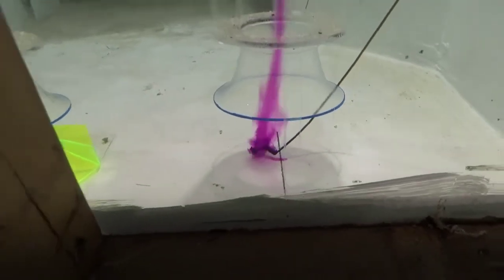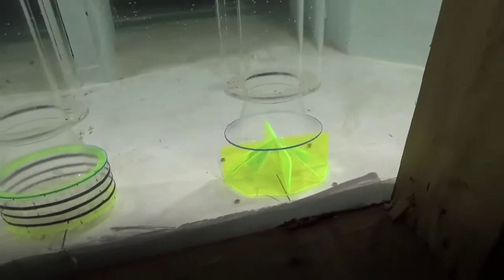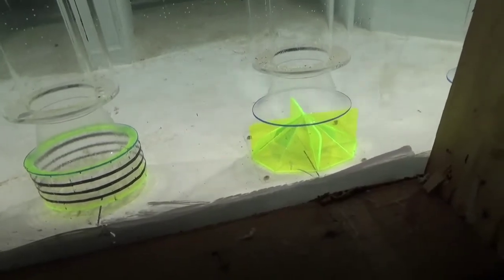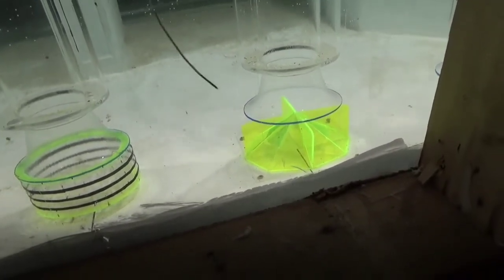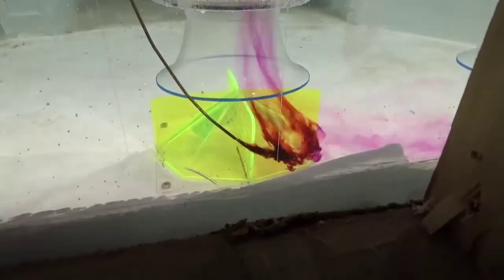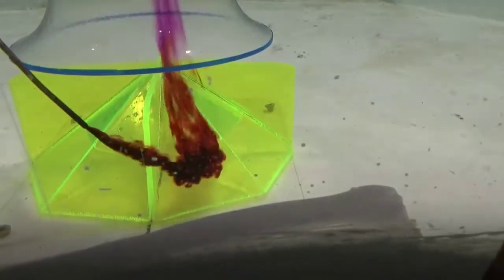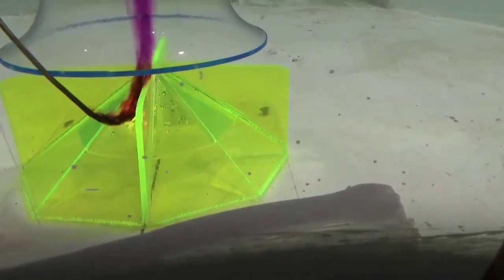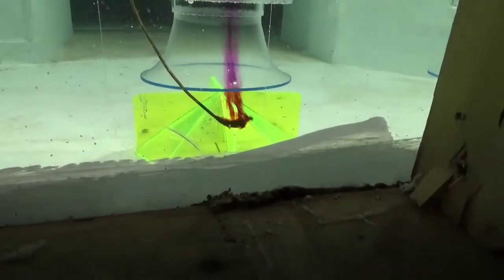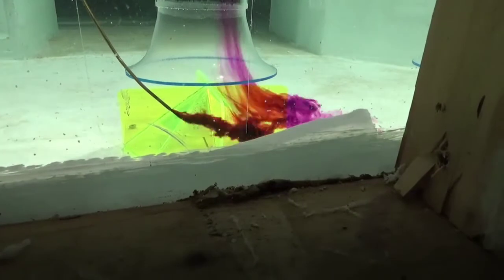Strong floor vortex. Let's move over here to the floor cone. This is going to get rid of the floor vortex, but see this circulation and swirl that we've got still going around the side and the back of that? It's actually going to separate off the back of this vane right here and get right on the vane, and it'll spin off the back of it and go right up into there. So that circulation, that swirl that we've got, you can see it's going sideways, is still putting more water on that side, and that's leading to that increase in pre-swirl over here.